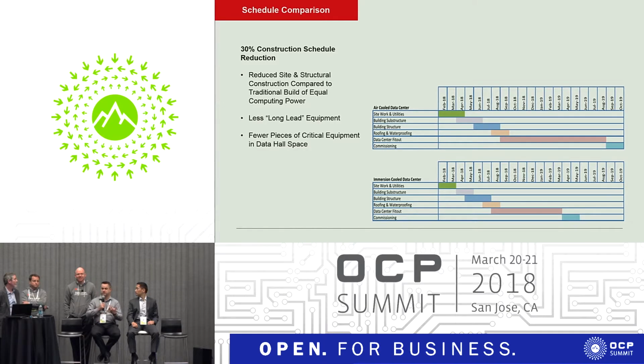Well, several of us will have items to add there, but from what I've seen personally, the fully developed ecosystem isn't quite there yet. A lot of it is waiting on the IT hardware to catch up. One of the things that makes any immersion solution more cost effective is when you need less fluid, and what allows you to get away with less fluid is the volume density of the actual hardware within that tank. If you were to take a conventional air-cooled server right now, strip the sheet metal off of it, strip the heat sinks off of it, and put it into a tank, you could do that, but you'd have about 90% air. Phil can probably talk a bit more about that because he's done those specific comparisons. But that's what I've seen.